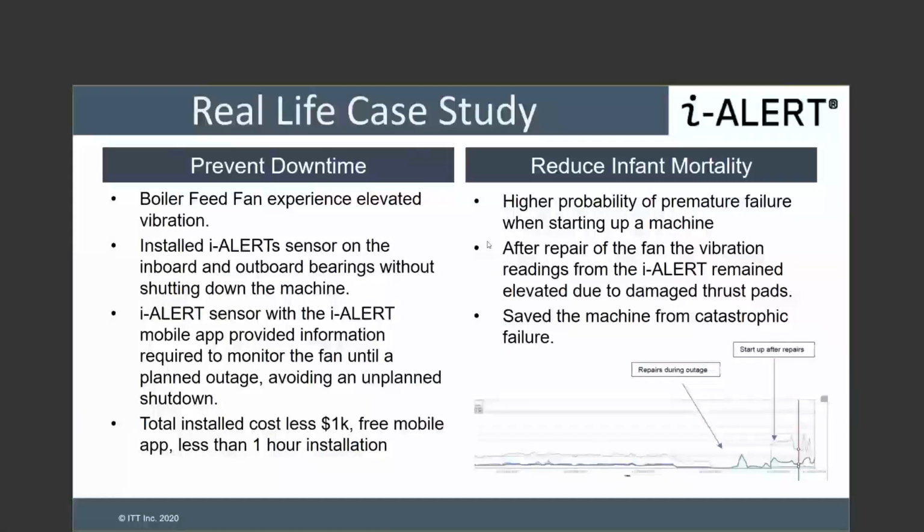and then trend the repair, and find another issue because of the trending analysis, and also using a data management tool to send notifications to the reliability team saying, hey, your repair was done, but we are still seeing some elevated vibration. So that's just a quick synopsis of how condition monitoring tools should be used, and how picking the right one definitely helped this particular reliability team.